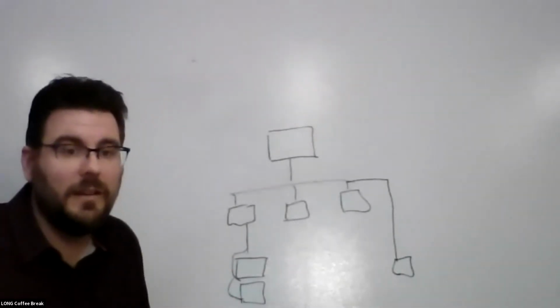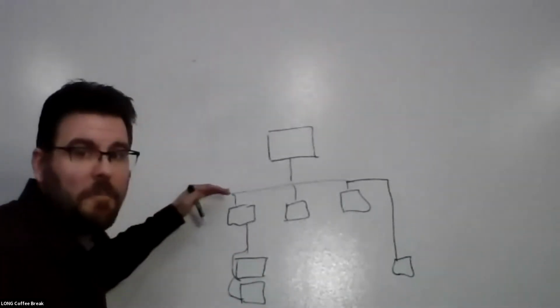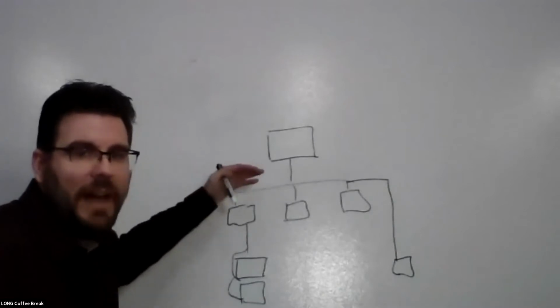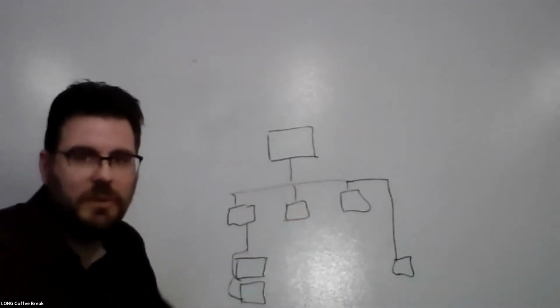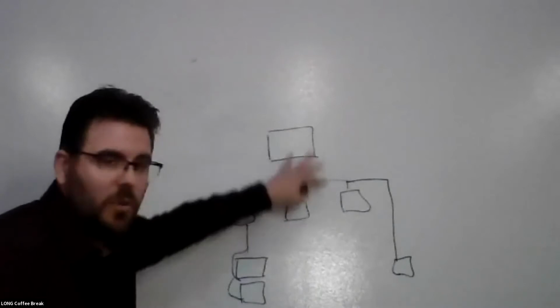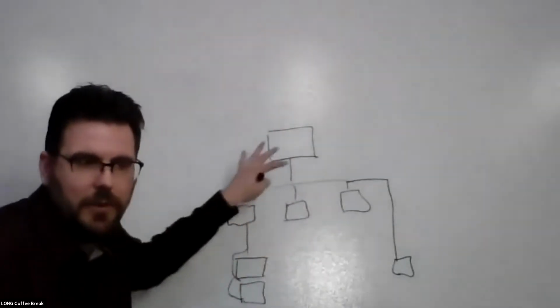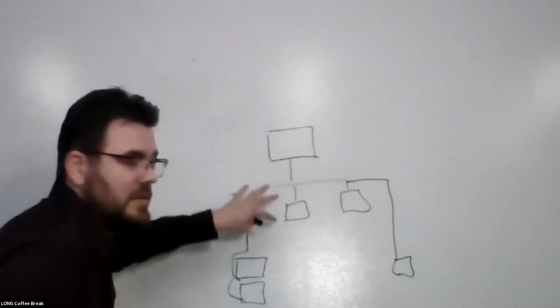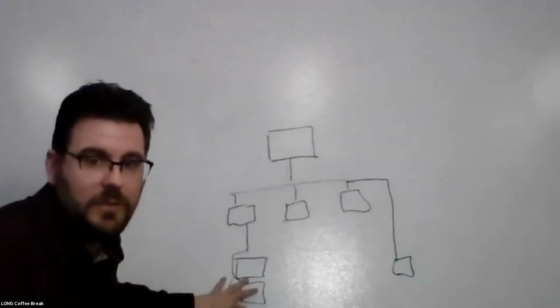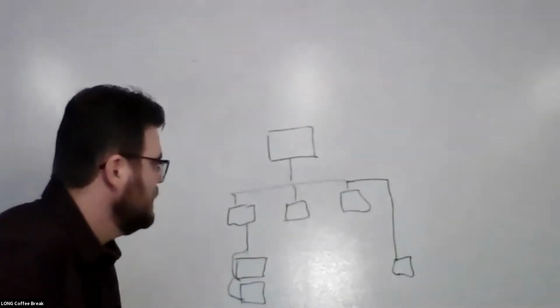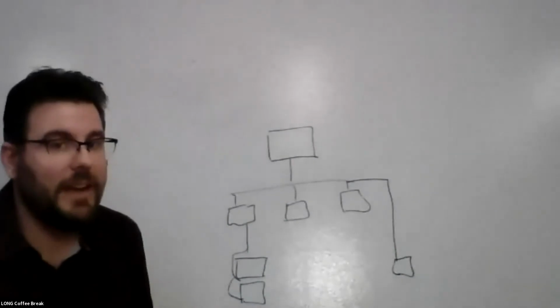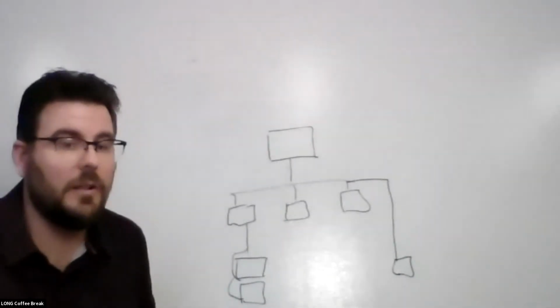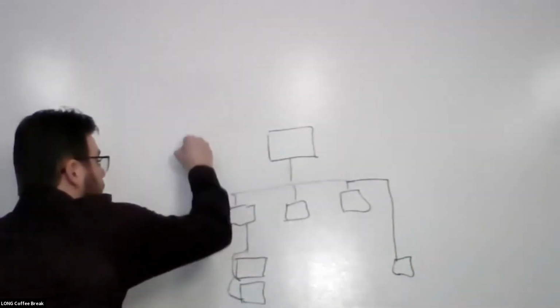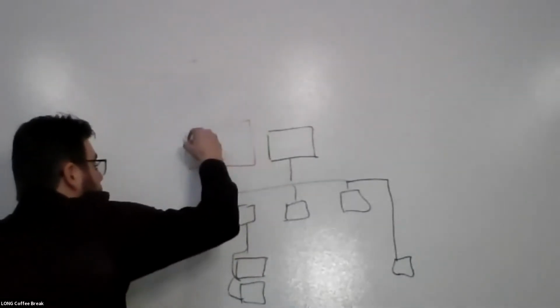We've also seen where now it goes to BACnet. But even with BACnet, they're afraid to make a change because they feel like this whole system needs to all go together, from their head end to the controller for the equipment down to the individual device. That can change, and it is available. There's a product out there called Niagara.